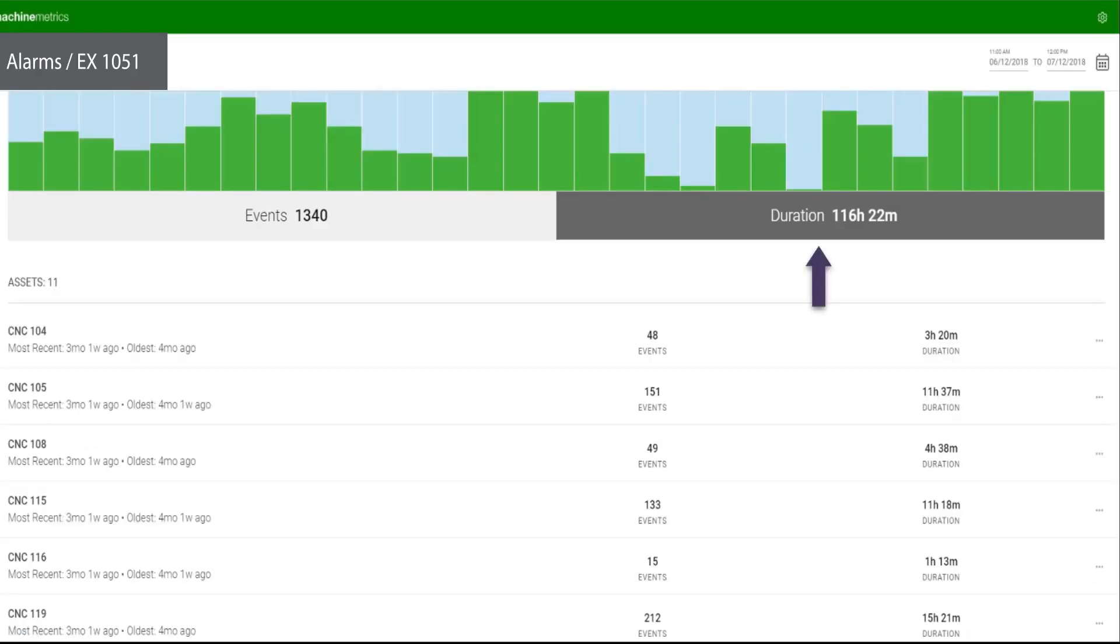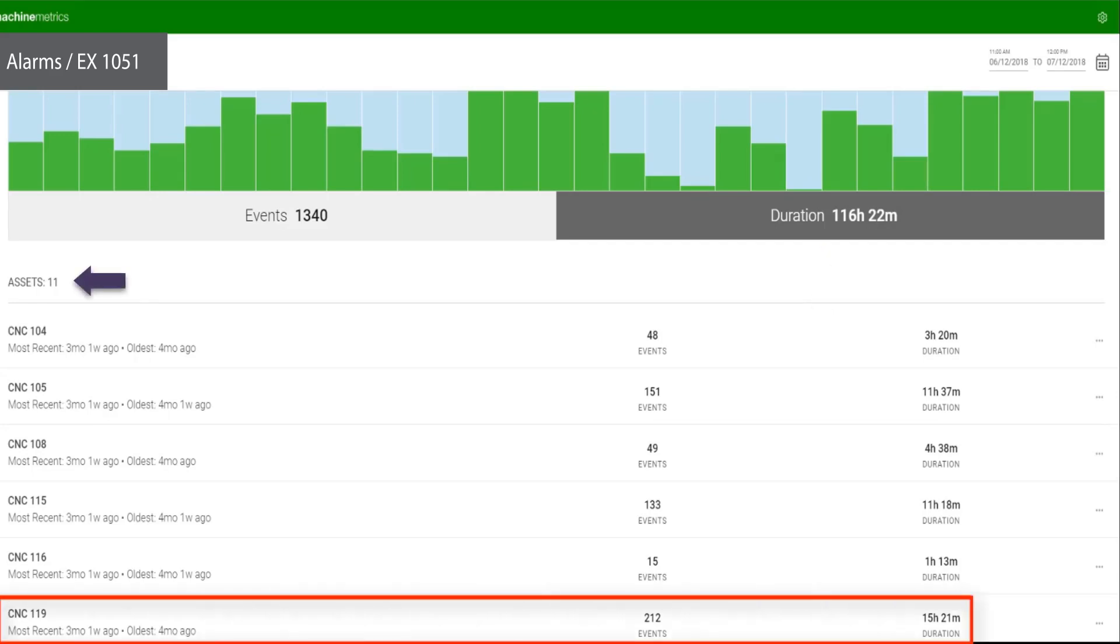Scrolling down on the screen shows a list of assets impacted by this error. CNC 119 has encountered 212 bar feeder alarms that have led to over 15 hours of downtime in the past month. By selecting the ellipses and clicking on overview, we can get a better picture of the asset's performance.